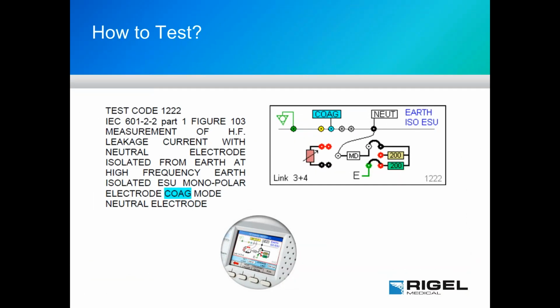So we're changing our circuit diagrams here a little bit. And I think I said 601-2-24 earlier, which is the infusion pumps test standard. So -2 is the generator standard. I apologize. And on the Unitherm, we have two separate dedicated 200 ohm resistors that we use for our high frequency leakage testing. And one of them, of course, is connected to earth ground, where our internal power load bank is not connected to earth ground.